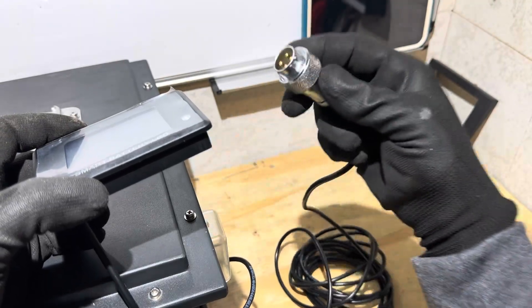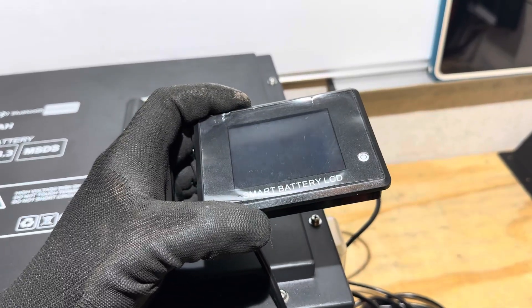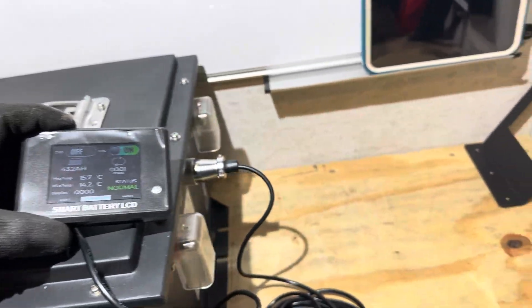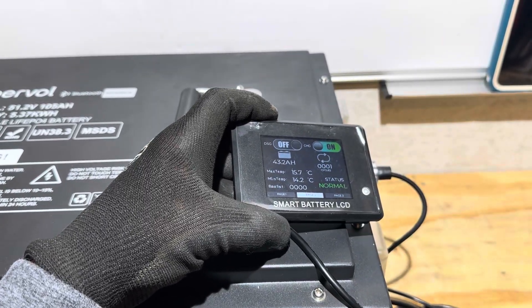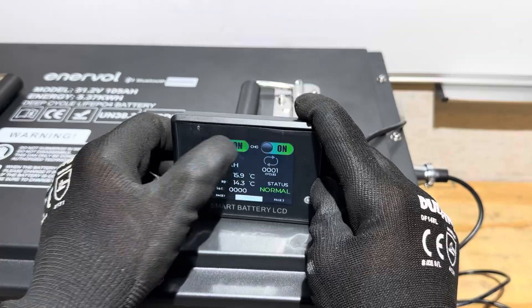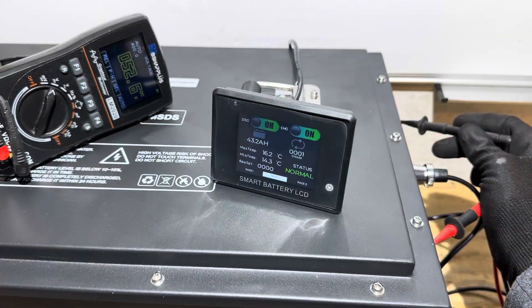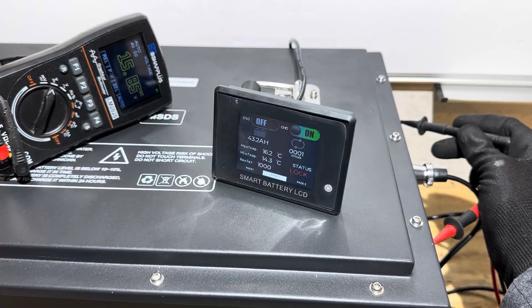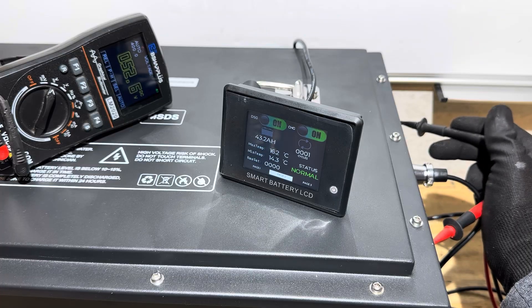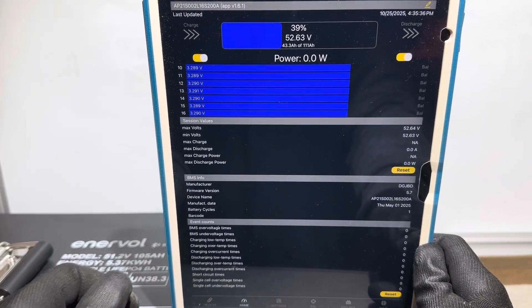Connecting the RS485 cord on the side of the battery — it has alignment teeth to line it up. There is power on the display without the switch being on. The discharge switch is off, so turning it on energizes the system. Testing with a meter connected: the switch properly cuts all voltage to the terminals, then instantly restores live voltage when turned back on. It's wired correctly.